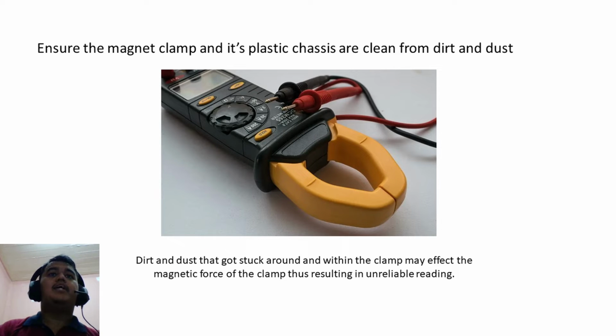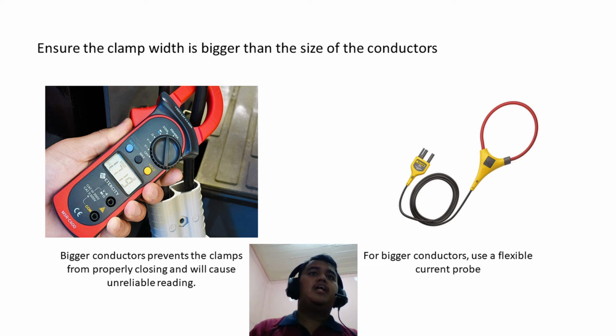Ensure the magnet clamp and its plastic chassis are clean from dirt and dust. Dirt and dust stuck around and within the clamp might affect its magnetic force, resulting in unreliable readings. Also ensure the clamp width is bigger than the size of the conductors.